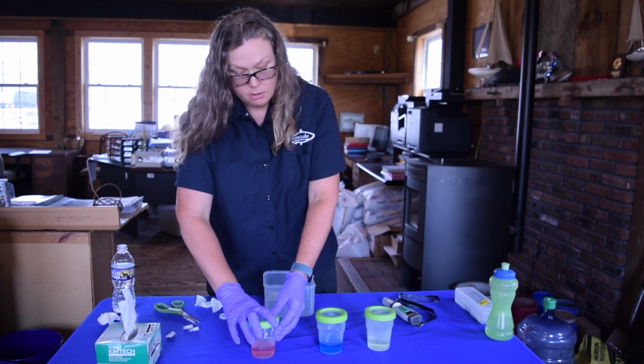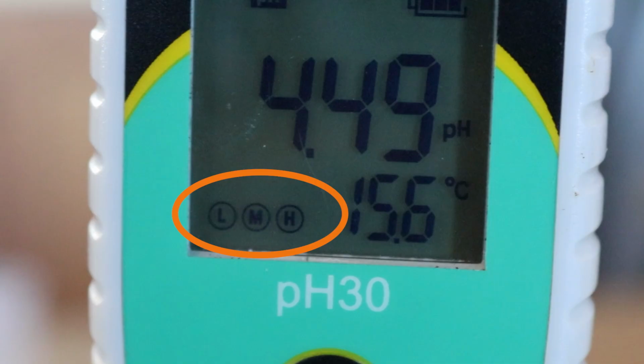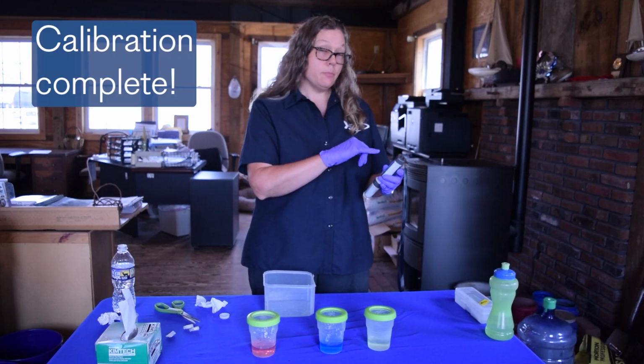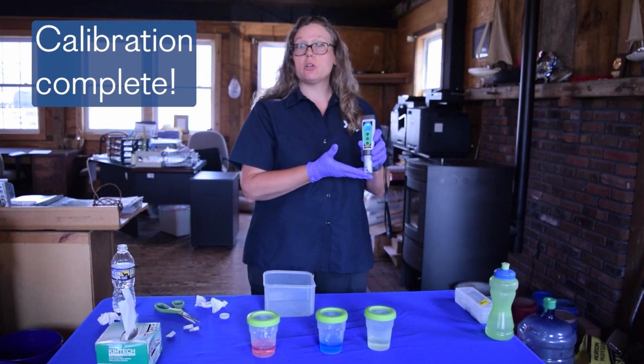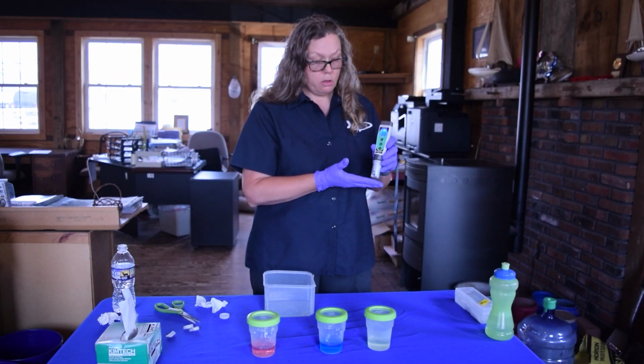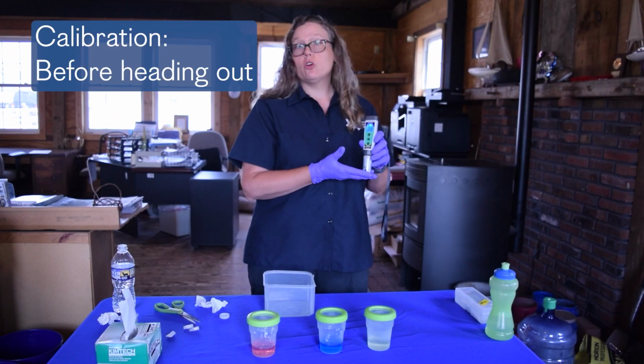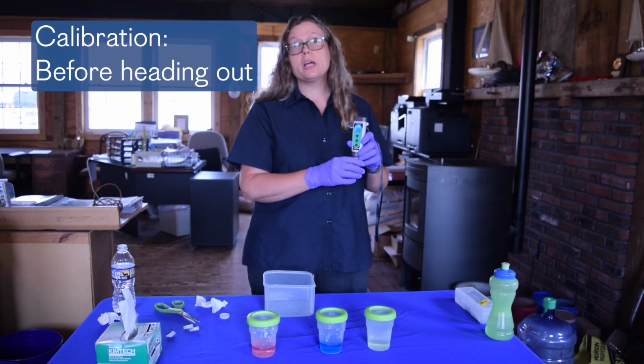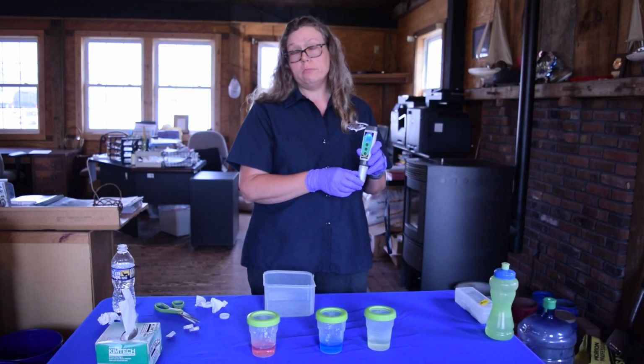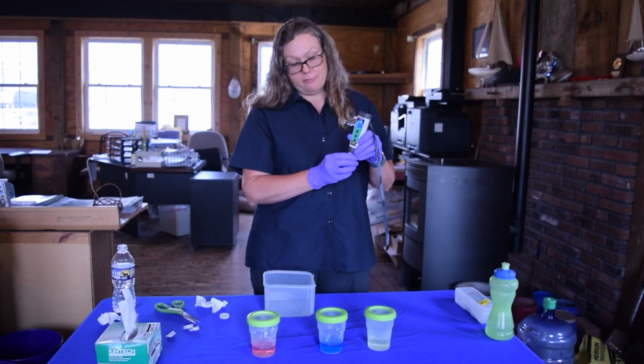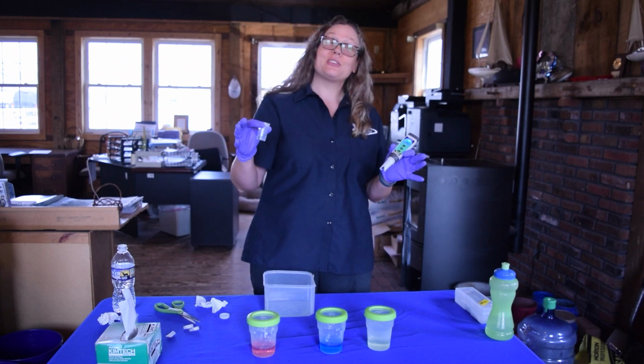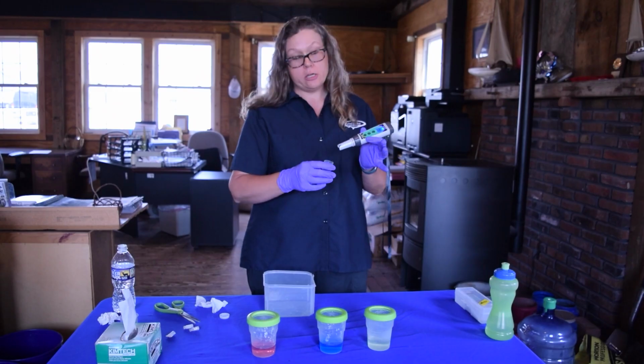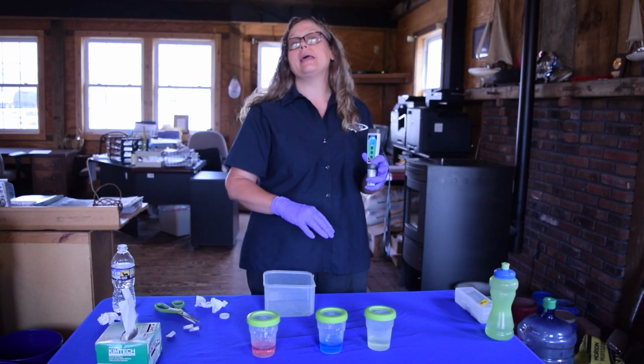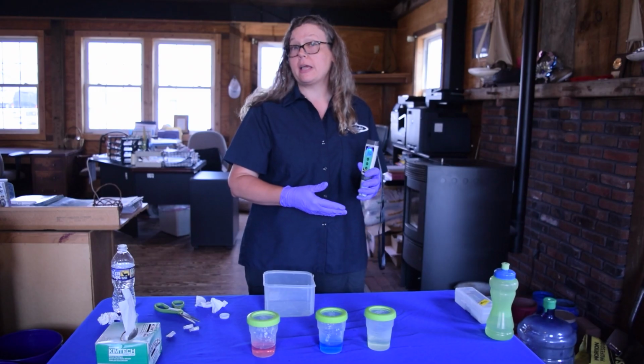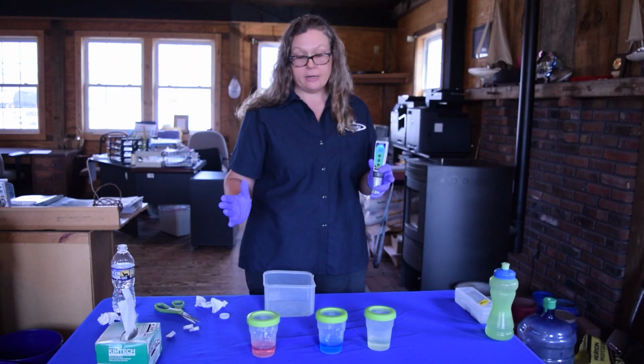Once we have completed the calibration and we see all three of our calibration points through the L, M, and H on the screen, at that point we return the storage cap to the probe. If you're going directly out in the field, you can go ahead and empty out your KCl or potassium chloride. If you leave this in the cap, a lot of times things happen in the field and you may knock it over. So that is why we recommend, hey, just go ahead and empty that KCl. You're going to be adding fresh KCl when you return from the field in any case.